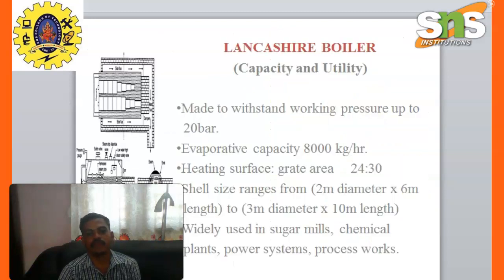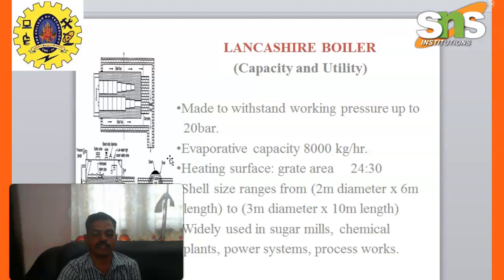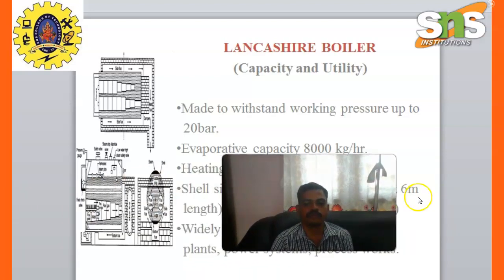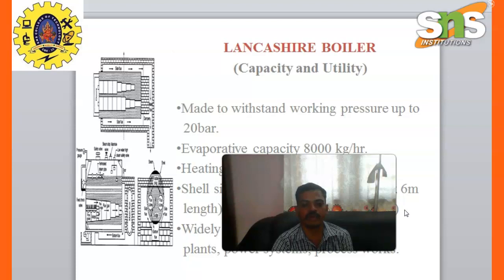The capacity and utility of Lancashire boiler: it is made to withstand working pressure up to 20 bar. Evaporative capacity is 8000 kg per hour. Heating surface to grate area ratio is 24.3. The shell size ranges from 2 meter diameter to 3 meter diameter into 10 meter length. Widely used in sugar mills, chemical plants, power systems, and process work.